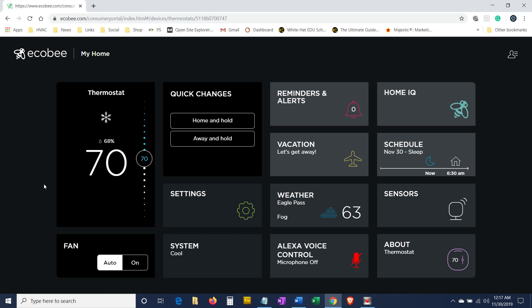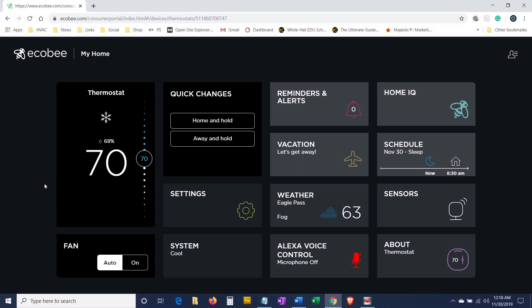I recommend go to Lowe's and buy the 18-5 solid thermostat wire. It's five wires in the bundle, all wrapped up. Just to be on the safe side, go ahead and get 18-7 or 18-8 wire and you'll have extra wires in the bundle. So in the future, if there's a problem, you can use those extra wires in place of whatever happens - if a wire breaks or something happens, you'll have an extra wire in the bundle to help you out.